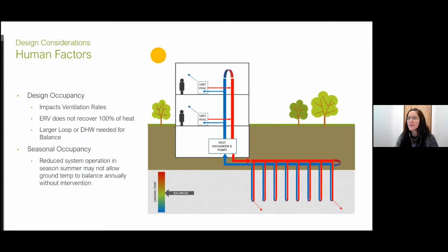What happens in the summer when potentially a significant number of occupants move out, and you were counting on that summer use of air conditioning to put heat back into the system and balance things out? If people move out and we aren't able to put heat back into the system, we'll be left with a colder ground loop on an annual basis when looking at those balancing cycles.